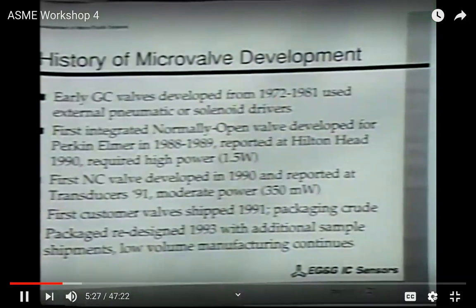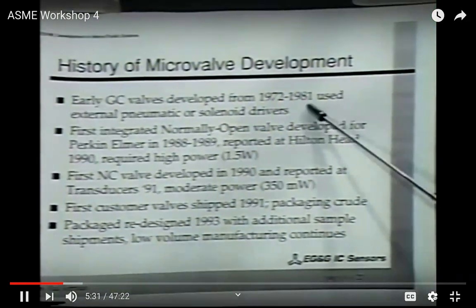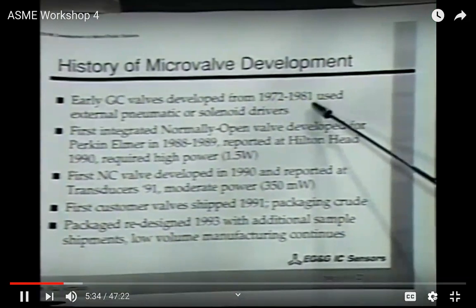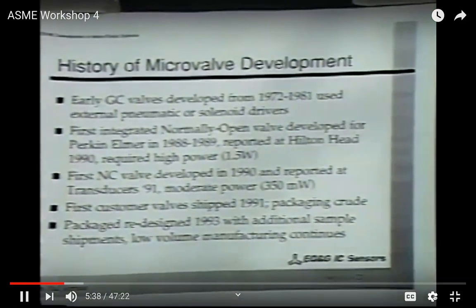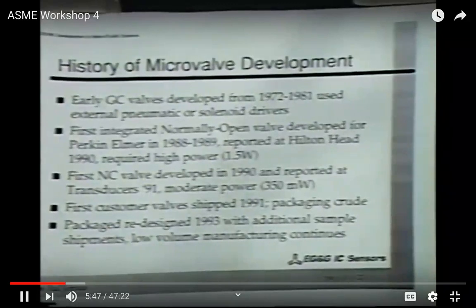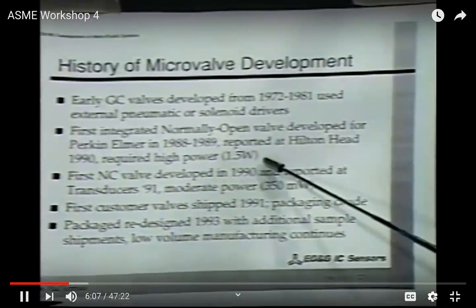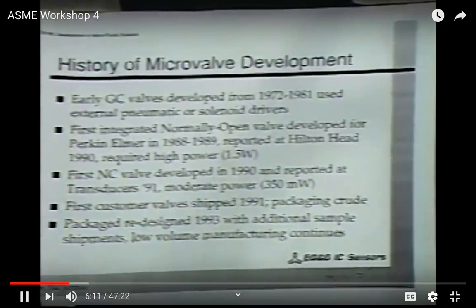Just to give you a little history, this part has been worked on for quite some time. Steve Terry and I developed a variety of different valves in the 1970s for use in a miniature chromatography system that I'll describe later. These used either pneumatic or solenoid drivers, and were quite successful in that application, but also quite expensive. A normally open valve was developed for one of our commercial customers, PerkinElmer, in 1988, and we reported that at the Hilton Head Conference in 1990. But it didn't have some of these thermal isolation features, and required quite high power, on the order of 1.5 watts.